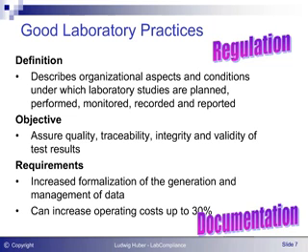For a GLP inspector, it should be possible to look at the documentation and easily find out who performed the study, how the experiment was carried out, which procedures were used, whether there were any problems, and if so, how the problems were solved. A frequent question is how much more this costs than normal analytical work. GLP operating costs may increase costs by 30% due to the additional documentation required.